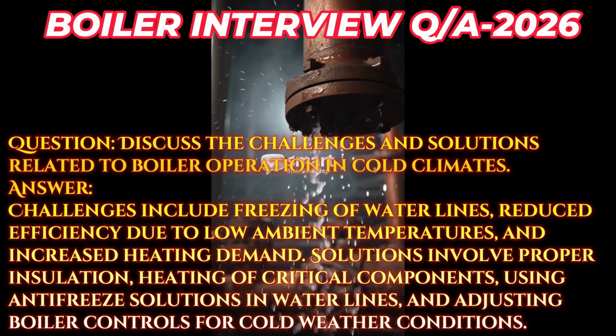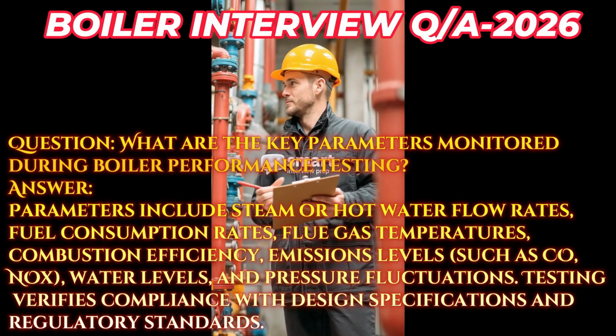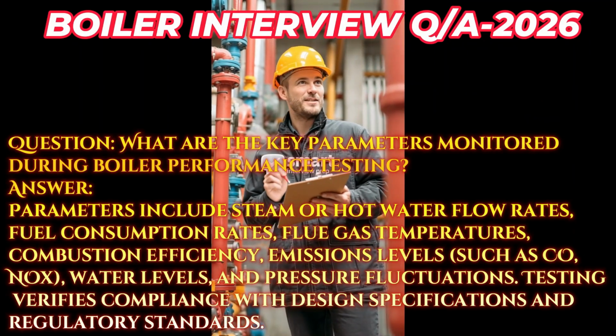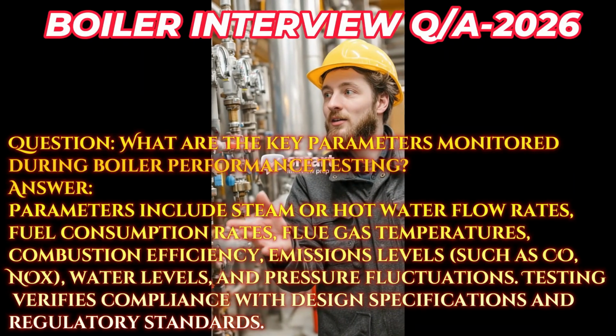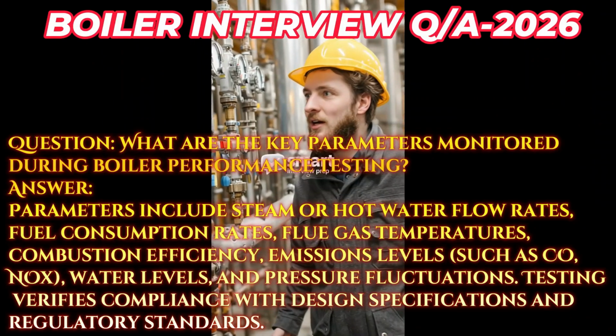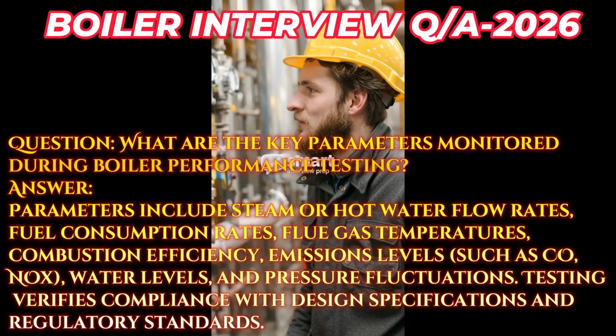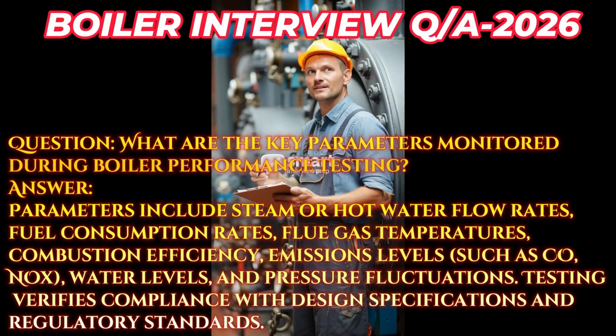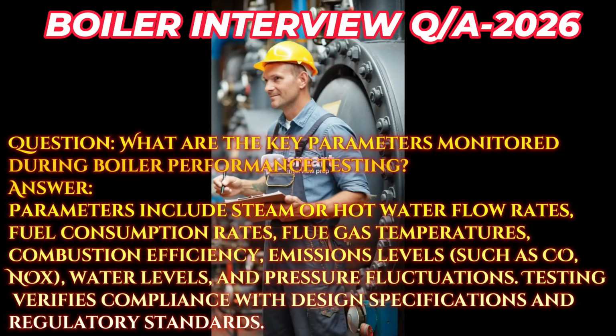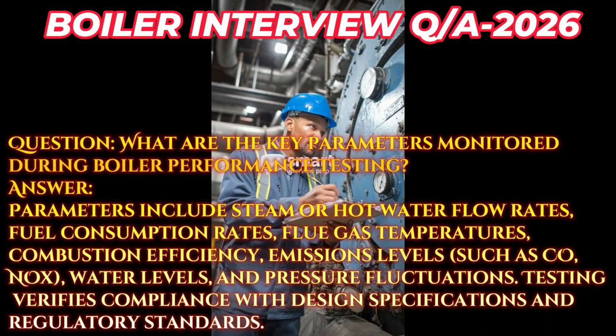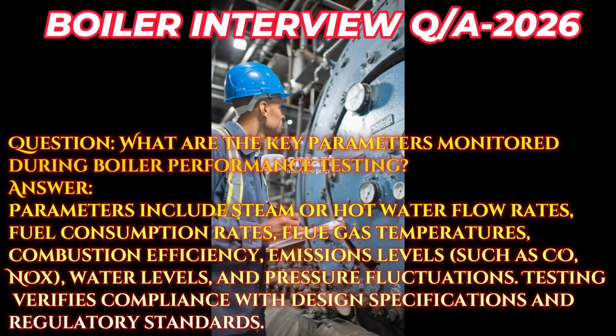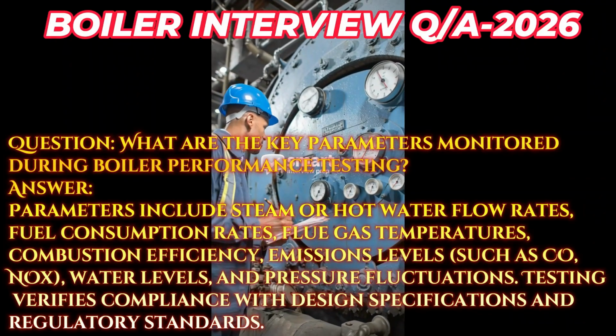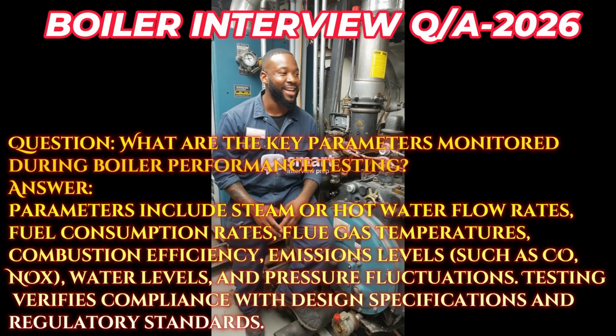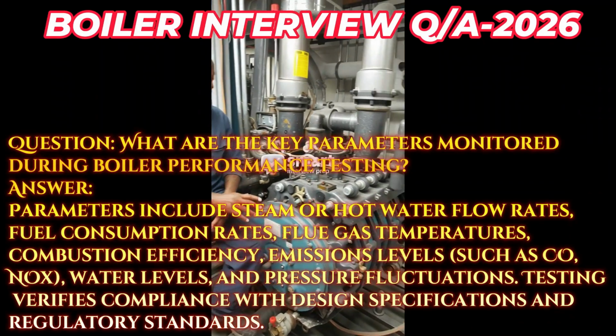weather conditions. Question. What are the key parameters monitored during boiler performance testing? Answer. Parameters include steam or hot water flow rates, fuel consumption rates, flue gas temperatures, combustion efficiency, emissions levels, such as CO, NOx, water levels, and pressure fluctuations. Testing verifies compliance with design specifications and regulatory standards.